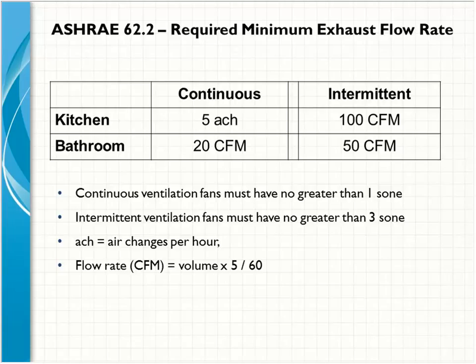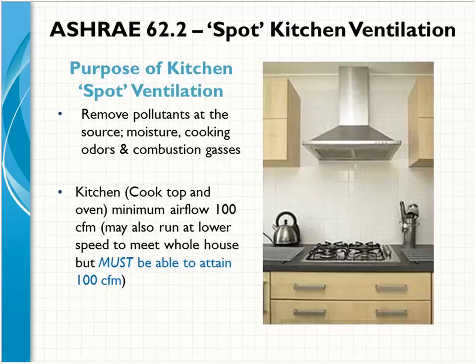In terms of sizing a bathroom fan, there are a couple of different approaches. You can use 1 CFM per square foot. You can do a volume calculation, whether it be V times 5 over 60, which is what's put in here. So there are a couple of different approaches that you can use to size a bathroom fan, for example, to exhaust the moisture.